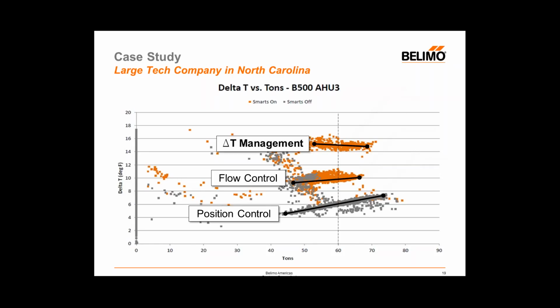So let's take a look at a single load point and try to quantify this a little clearer. If we look at 60 tons of cooling, in position control mode, 60 tons of cooling was done at 6 degrees of delta T, and if we use our tons equals GPM times delta T over 24, all that stuff, we can calculate that 240 gallons a minute were required to create that 60 tons of cooling.